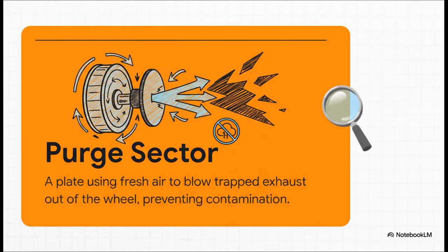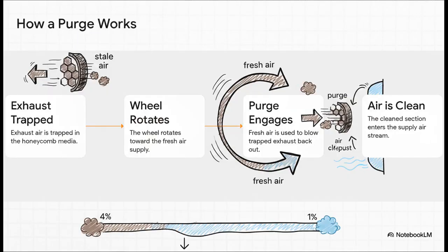They use this clever little device called a purge sector. It's basically a stationary plate that's designed to clean out the wheel as it spins, and it uses a tiny bit of the fresh air to do the job. Pretty smart. So here's how it works.